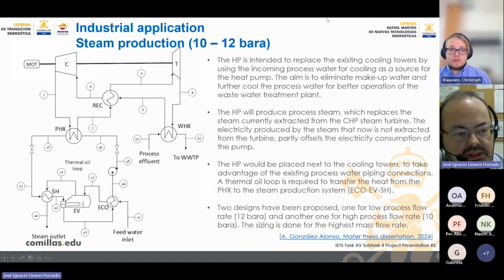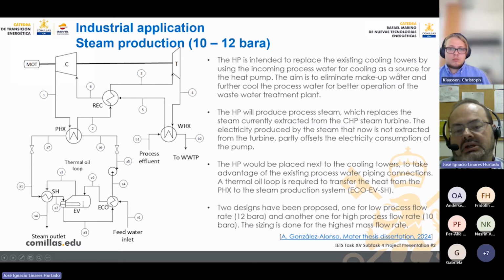And finally, the last application with more detail, because last year we supervised a master thesis dissertation about this topic, and it can be found here in Spanish, but with an extended summary in English. In this application, the heat pump is intended to replace the existing cooling towers of a factory, using the incoming process water for cooling in the tower as a source for the heat pump here. The aim is to eliminate the makeup water and further cool the process water in order to enhance the performance of the wastewater treatment plant.